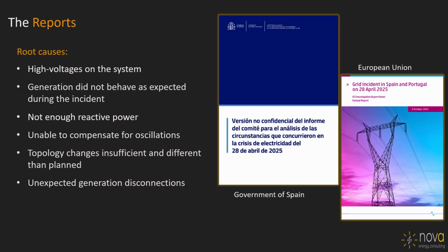Voltage was just climbing well beyond what was safe and supposed to be, which meant they were not able to compensate for oscillations. Also, what you do on the network in terms of topology, if you have no other recourse, is change the way the network is connected. Imagine grabbing your beam, but the beam has connections in itself, so you try to split it into a couple halves or thirds and run them independently so they don't drag each other. There were a bunch of switching operations done on the day, but that was also insufficient.